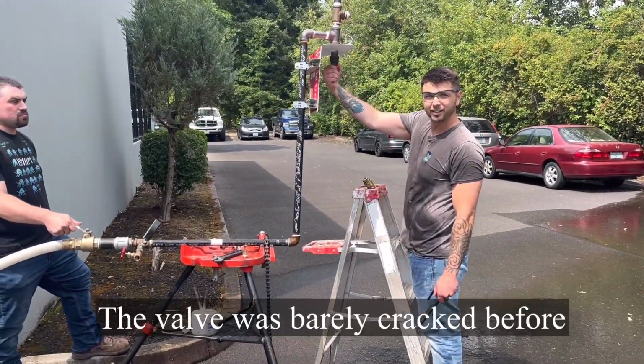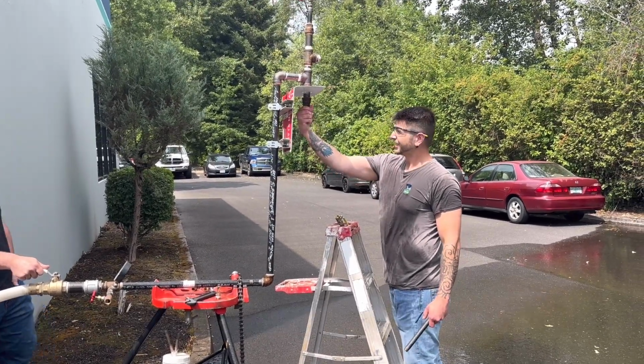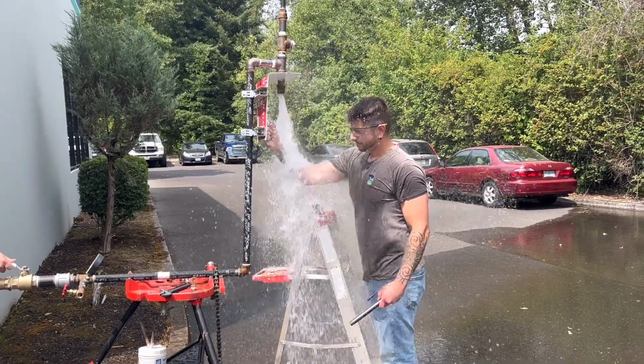What was it before? It was 70, but I had it throttled down where it was barely leaking. So now you're going to have full flow, like you pull one off a real live system. So when this pulls out, you'll be about 50.